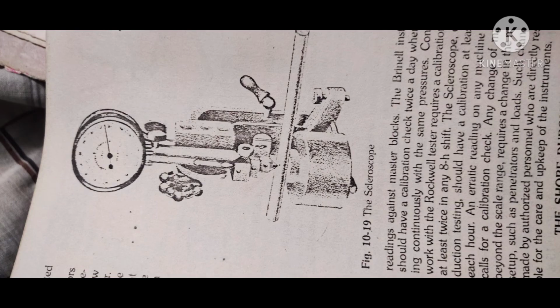The scleroscope hardness test. The scleroscope hardness tester, as shown in this figure, is an instrument used for testing the hardness of metals. This instrument tests not by indentation but by rebound. It has a diamond-pointed ball that drops through a glass tube onto the material being tested. This tube is mounted with a graduated scale, and the rebound of the ball or point is caught by the eye at its peak, and the corresponding graduation is then read. The instrument is also made with a direct reading head which records the amount of rebound. A soft ball is provided for the testing of non-ferrous metals, and readings are taken from the same scale.